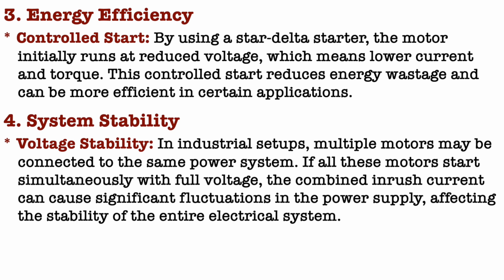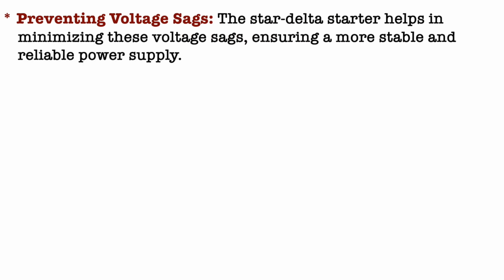In an industrial setup, multiple motors may be connected to the same power system. If all these motors start simultaneously with full voltage, the combined inrush current can cause significant fluctuation in the power supply, affecting the stability of the entire electrical system. Next one is preventing voltage sag. The star delta starter helps in minimizing this voltage sag, ensuring a more stable and reliable power supply.